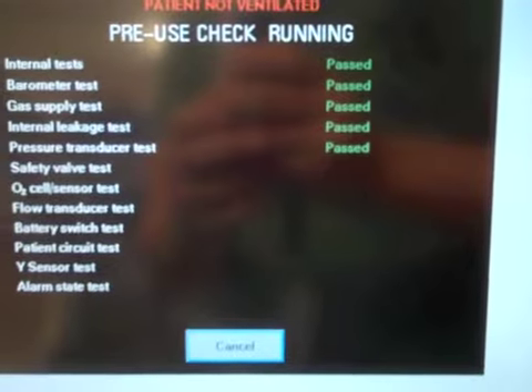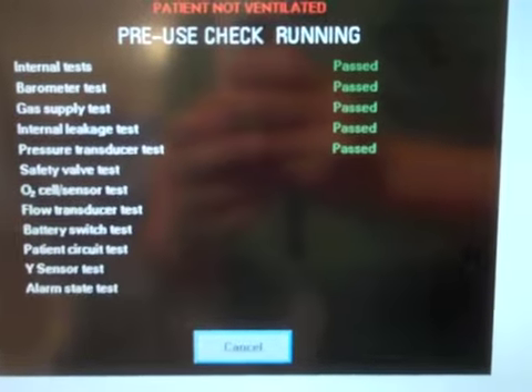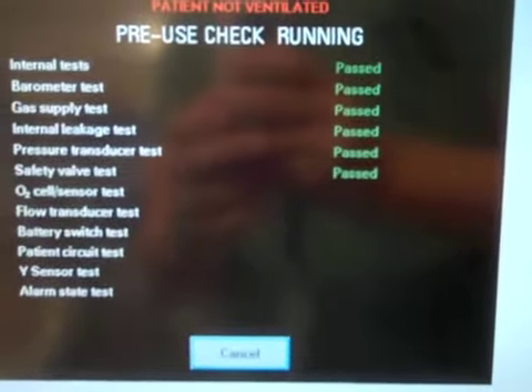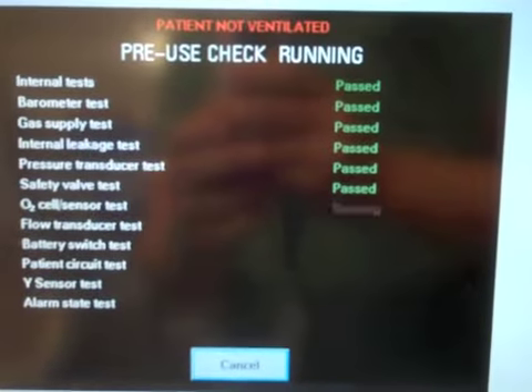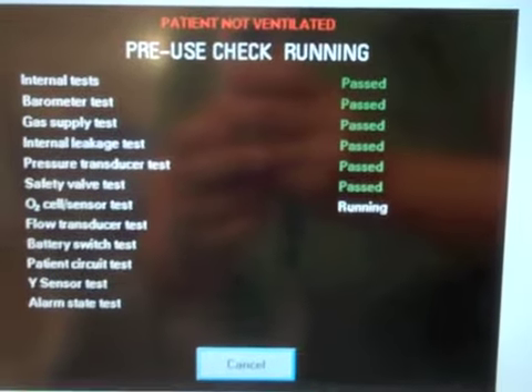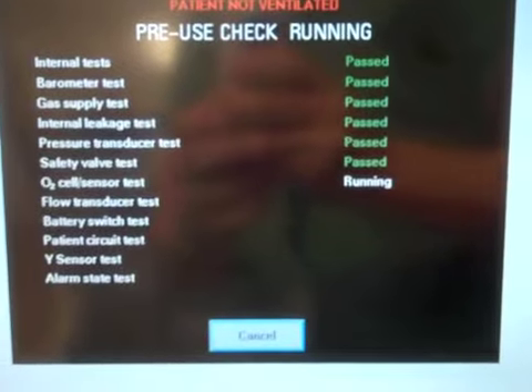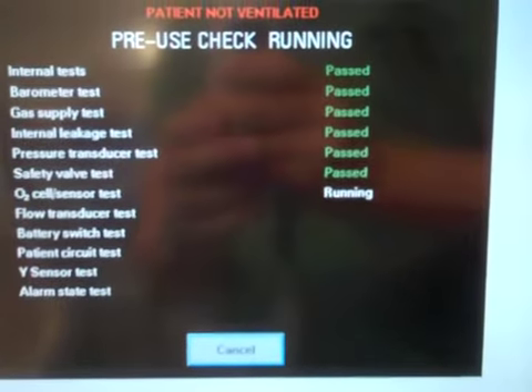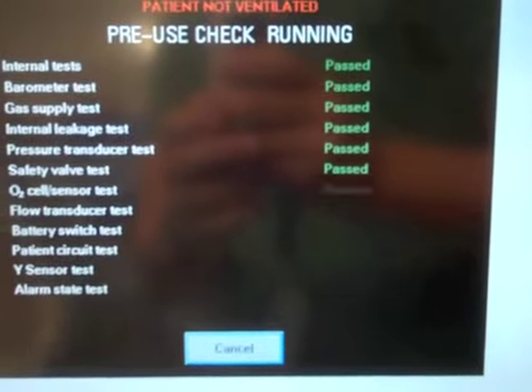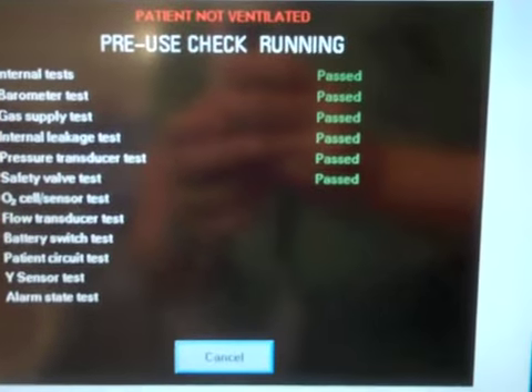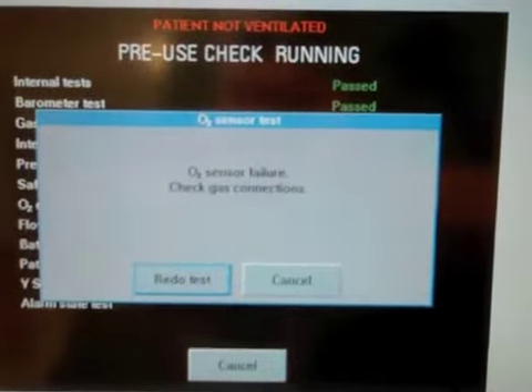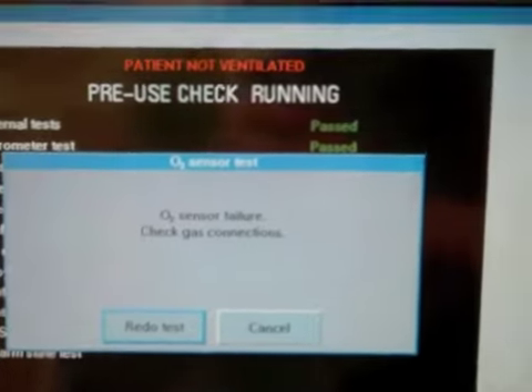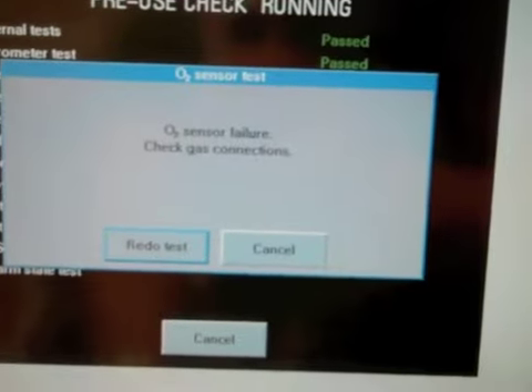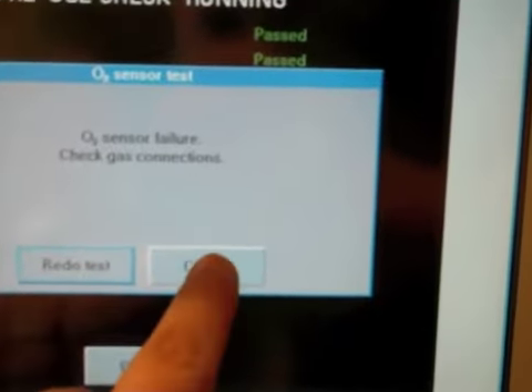And you can hear it going through its checks, pneumatically powering the circuit and internal components as it goes. So this is doing the O2 sensor. I fully expect this to fail, since I don't have this plugged into oxygen. So there you go, oxygen sensor fails, telling me to check gas connection. Well, if I redo the test, I can redo that test all day long, it's still going to fail, so I'm just going to cancel out of it.